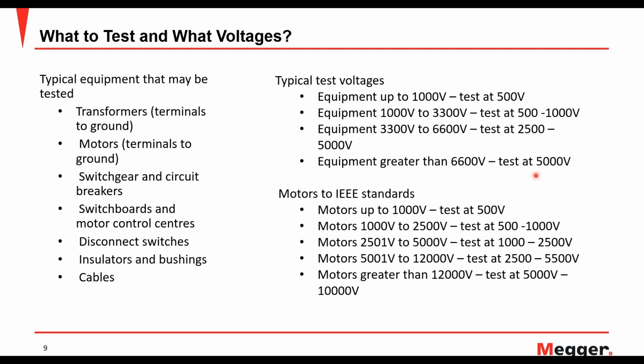What to test and at what voltages. Typical equipment that may be tested can be transformers, motors, switchgear, circuit breakers, switchboards or motor control centers (MCCs), disconnect switches, insulators, bushings, cables. Pretty much everything that is in a substation can have an insulation resistance test done on it. And this is what I was talking about, typical test voltages. Equipment up to 1000 volts, test at 500 volts. Equipment at 1000 to 3300 volts, test at 500 to 1000 volts, and so on. Motors have slightly different IEEE standards compared to everything else, so those are listed here as well. They have slightly different limits, as you will notice, than your typical other equipment. Those are your typical test voltages for different equipment ratings.